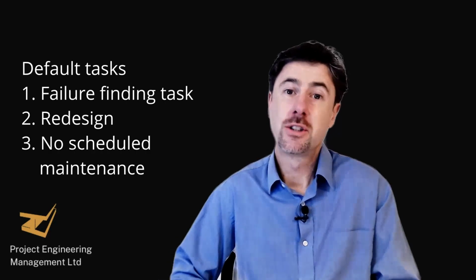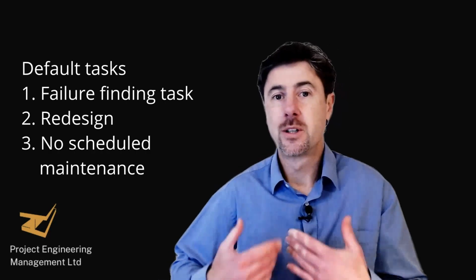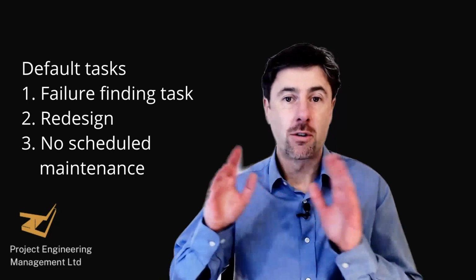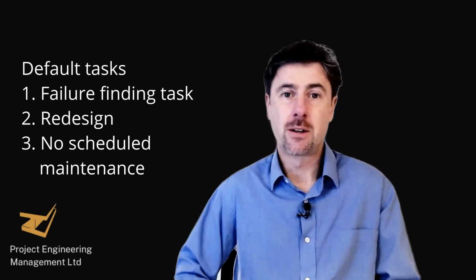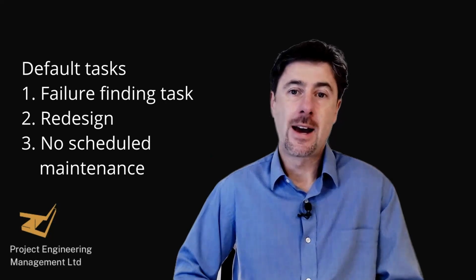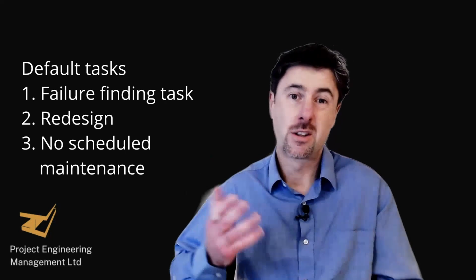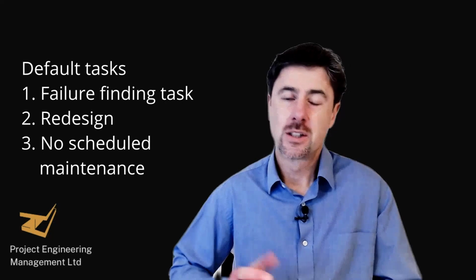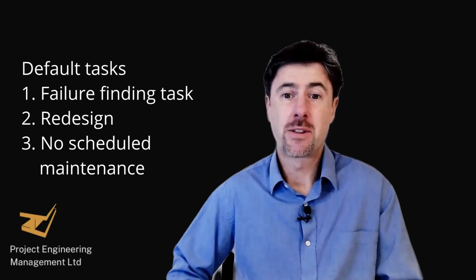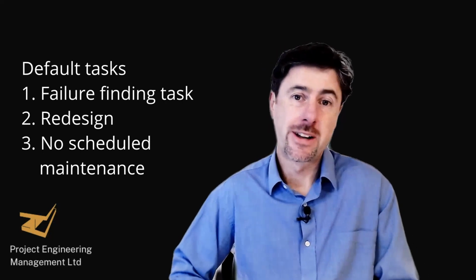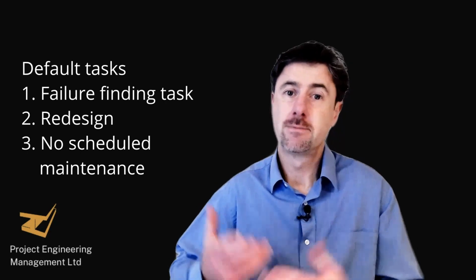Number 3, no scheduled maintenance. In other words, just run it till it fails. Perhaps there's an electronic sign advertising the company on the side of the storage tank, and the consequence of the failure if those lights go out are pretty low. So it's probably not worth us doing any maintenance on that. Just run it until one of the lights fail, replace it, and on we go.